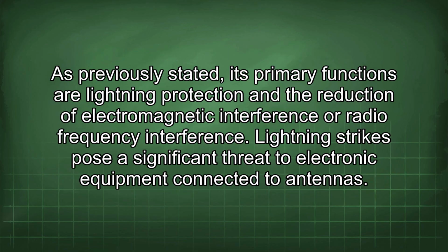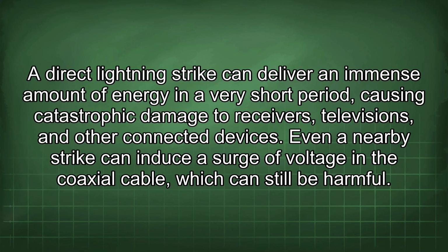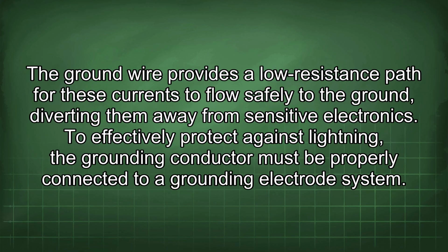As previously stated, its primary functions are lightning protection and the reduction of electromagnetic interference or radio frequency interference. Lightning strikes pose a significant threat to electronic equipment connected to antennas. A direct lightning strike can deliver an immense amount of energy in a very short period, causing catastrophic damage to receivers, televisions, and other connected devices. Even a nearby strike can induce a surge of voltage in the coaxial cable, which can still be harmful.